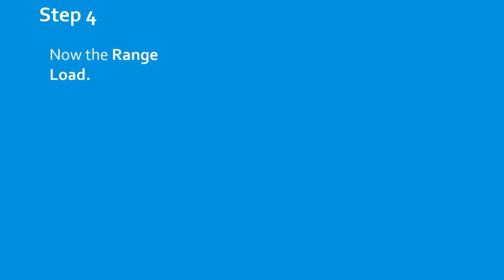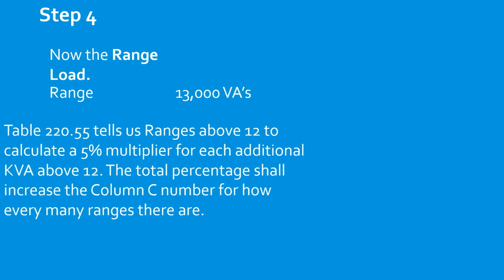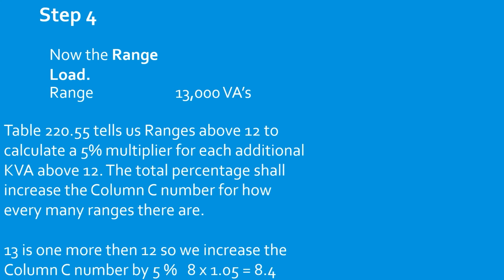Now the range load. Our range is 13,000 VAs. Table 220.55 tells us that for ranges that are above 12, we calculate a 5% multiplier for each kVA above 12, like we learned previously. So the total percentage shall be increased by the column C number for however many ranges there are. So in this case, we have 1. We are also 1 over 12, so that is going to give us a 5% multiplier. So we go to column C for 1 range. That's going to be 8 kVA, and we increase that by 5%, which you just multiply by 1.05. That's going to give you 8.4 kVA.